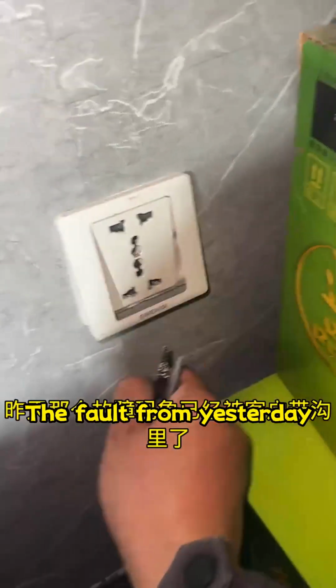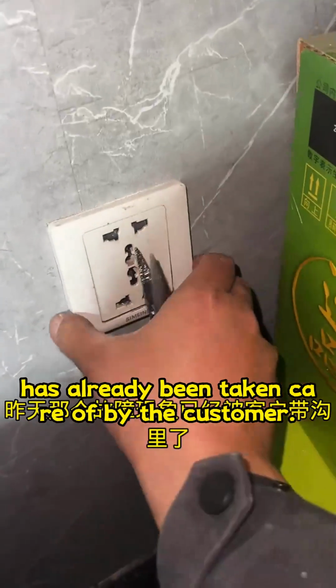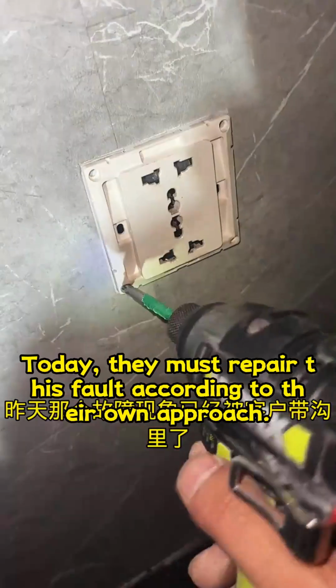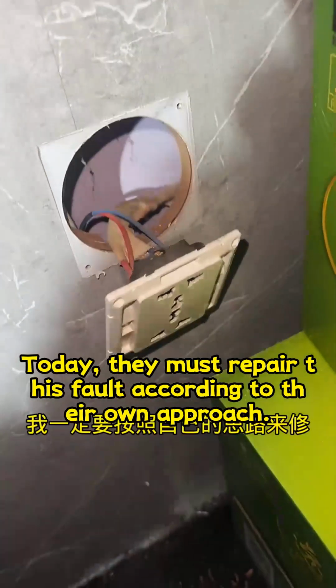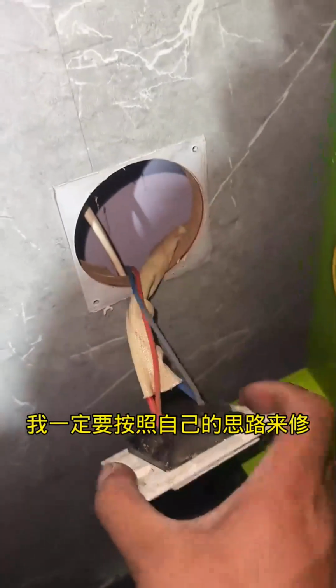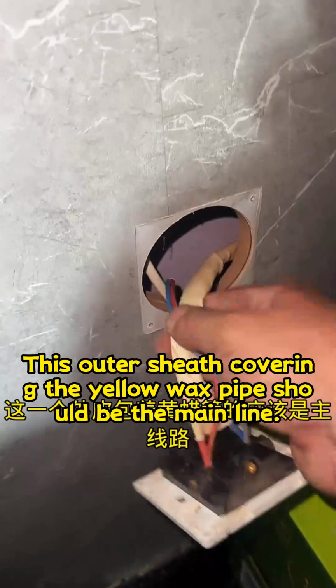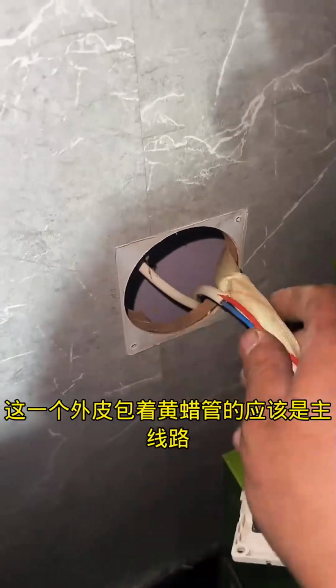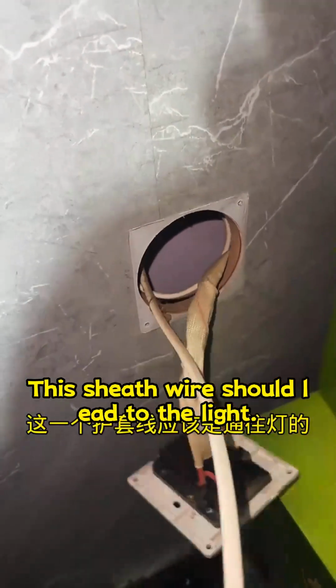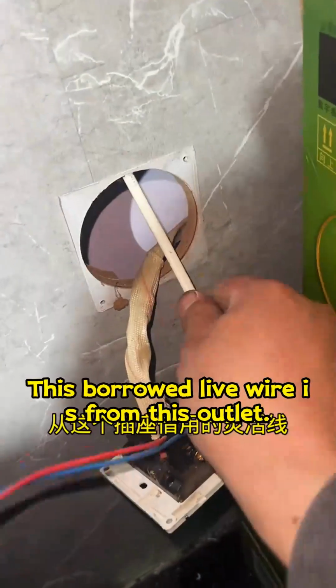The fault from yesterday has already been taken care of by the customer. Today, they must repair this fault according to their own approach. This outer sheath covering the yellow wax pipe should be the main line. This sheath wire should lead to the light. This borrowed live wire is from this outlet.